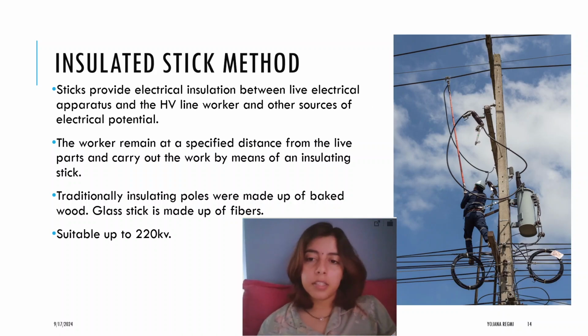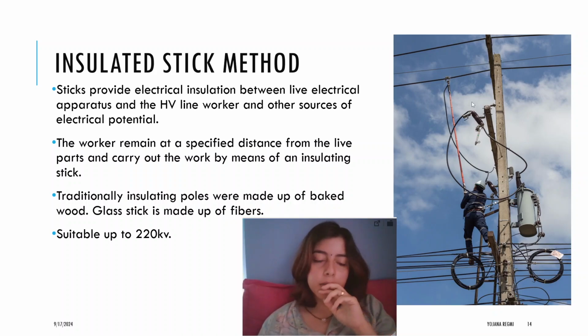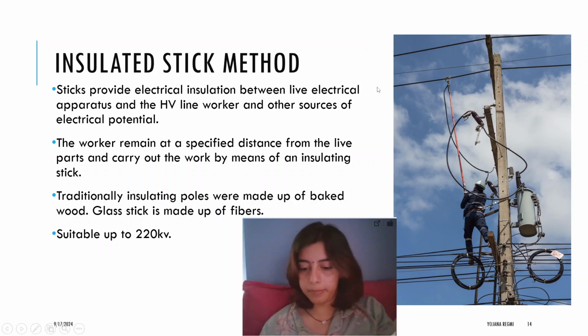This stick provides insulation between the line and the worker, so the person is not in direct contact with the line and won't get a shock. The worker has to remain at a specified distance - it's not that a worker can come very close to the line and just use a stick to do the work. You have to maintain the distance prescribed by the agency, with specifications based on the kilovolts you're working with. So this is the insulated stick method.